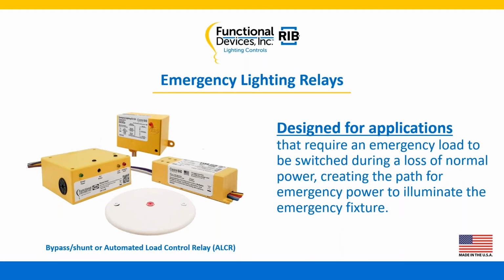First, our products are designed for applications that require emergency load to be switched during a loss of normal power. Basically, what we're doing is creating a path for emergency power to energize the emergency fixture.